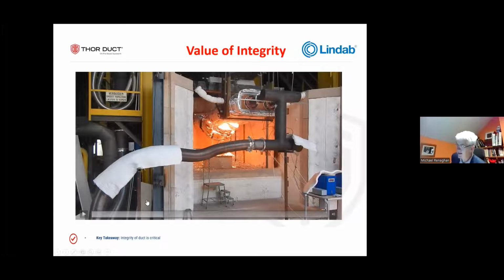Okay, we don't need to see any more of it. But basically, you can see what's happening here. So the temperature is so hot on the metal that the insulation's focusing that temperature on the metal itself, so it's softening. It goes through what we call an elastic phase and a plastic phase. During the elastic phase, it creates a tension, a pressure, a force. And so the duct has to be able to cope with that force pressure. But after the elastic phase, it goes through the plastic phase, it's all soft.